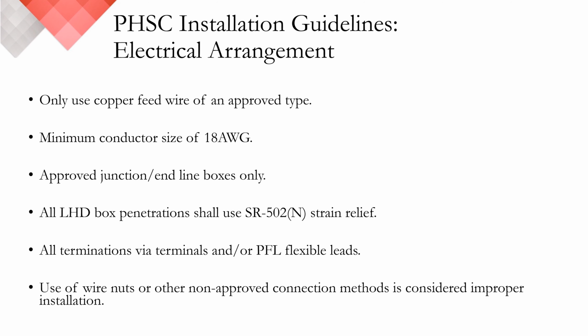Pay close attention to the type of detector you're using and use only the appropriate feed cable. For PHSC and PLR series, use only approved copper feed cable with a minimum conductor size of 18 gauge. For CTI, we're dealing with the thermocouple principle, so we'll get into that in a couple of minutes, but different feed cable. Our junction boxes have been selected to meet a wide range of environmental conditions.